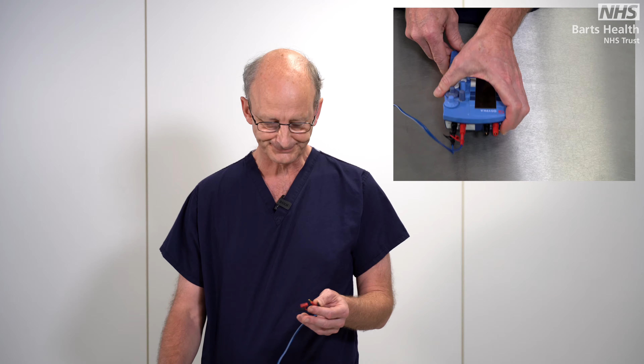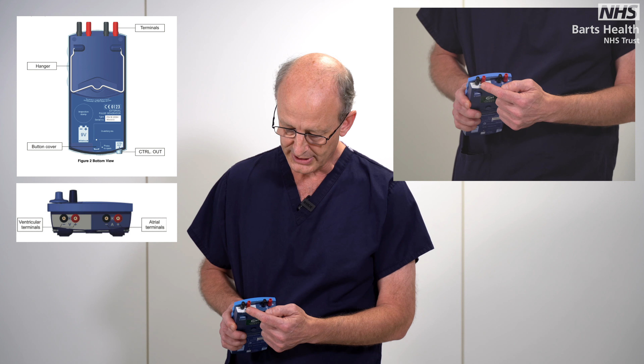So this is the OSYPKA pacing box. This is the model 203H. And we're going to look at some of the main features of this box. First of all, connecting the box to the patient. So if we have a look at the top end of the OSYPKA pacing box, you can see that there are four terminals, and these are coloured red and black. There's two sets of each. One comes out of an area of the box which is white and labelled V, and one comes out of an area of the box which is blue and labelled A. And these are the terminals that we can connect our pacing lead to.